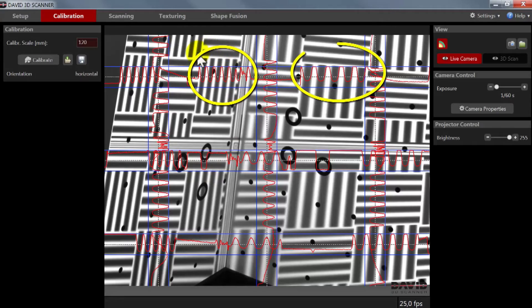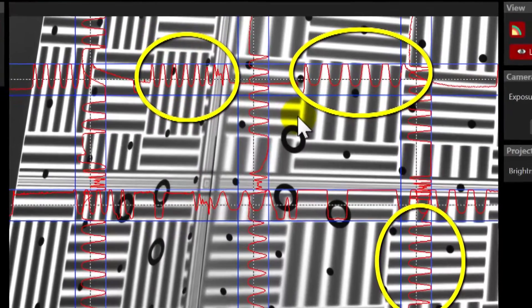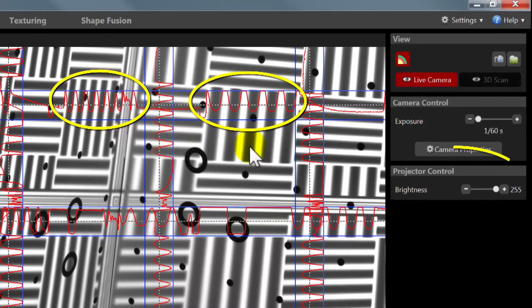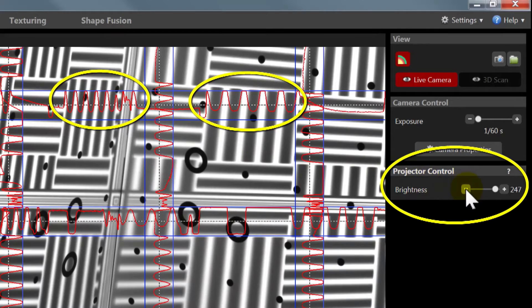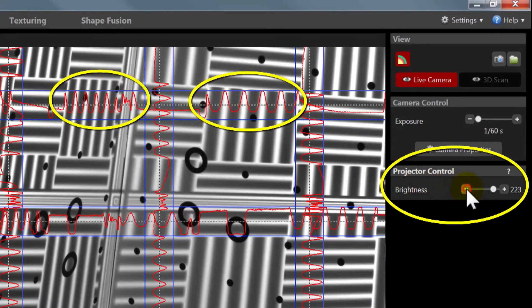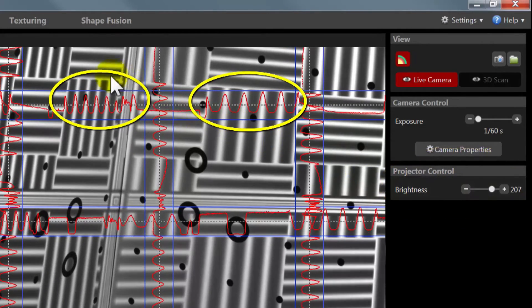Now it may be that the calibration panels are much brighter than the scanned object, then the sine waves will now be distorted. Decrease the projector brightness setting temporarily to get clean sine waves that are not cut off.